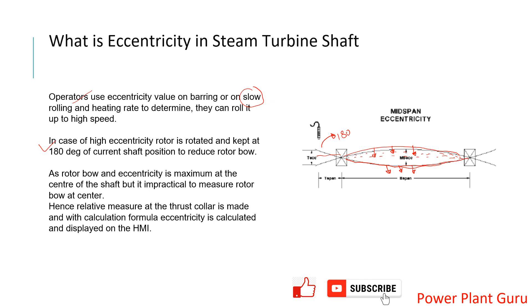Another important concept people were asking about is how instruments measure eccentricity. The maximum bow is in the middle of the shaft, but there is nothing to measure there because that area is occupied by blades — stator blades, rotating blades, etc. Whatever the bow is, it will follow a particular curve from the bearing end, like a cantilever position, where the thrust bearing and collar are located.